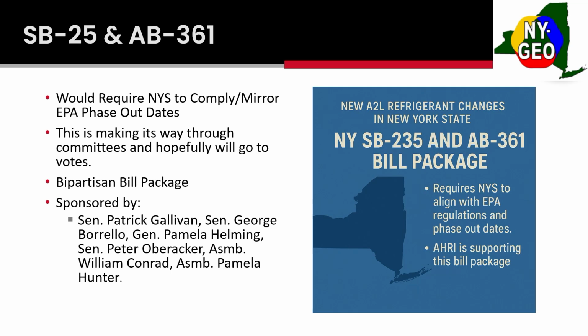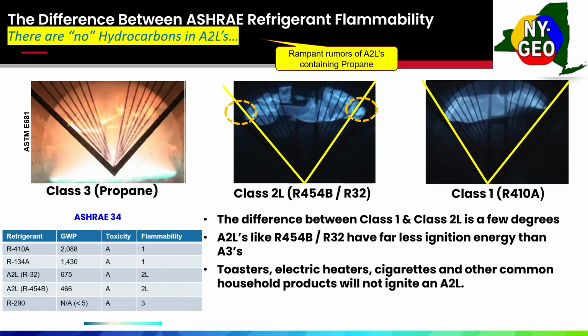So let's talk about those A2L refrigerants and propane, A3. When we first started talking about A2L refrigerants, people heard the word flammable and got scared. That was kind of the first reaction: oh no, is the building going to blow up? Is there going to be a big fire? Kind of looks like the Hindenburg blowing up a little bit. But in reality, A2L refrigerants are only marginally more flammable than 410A.